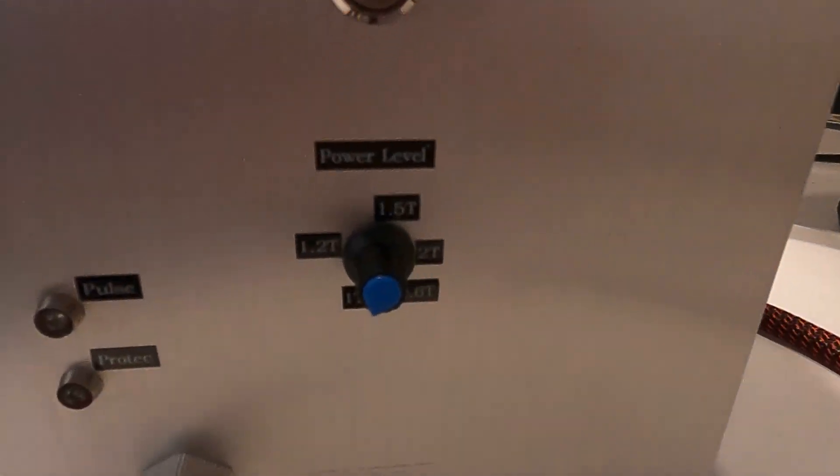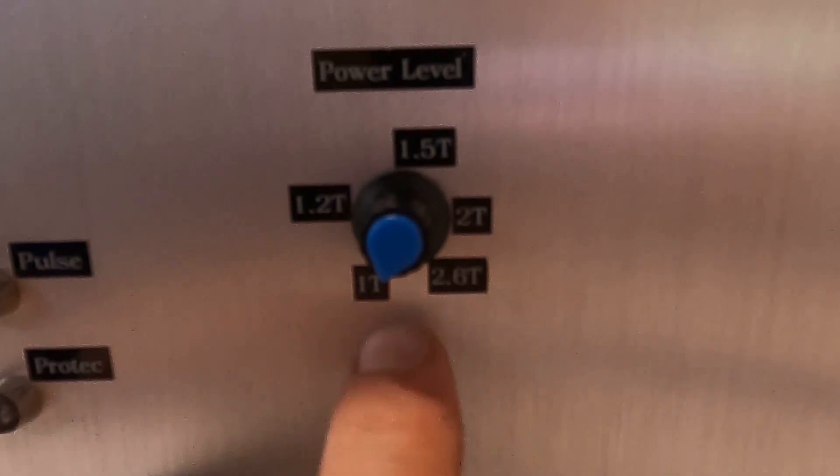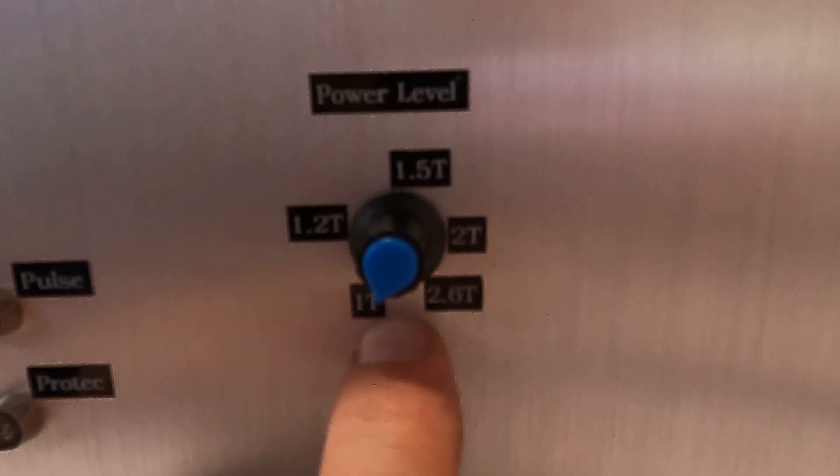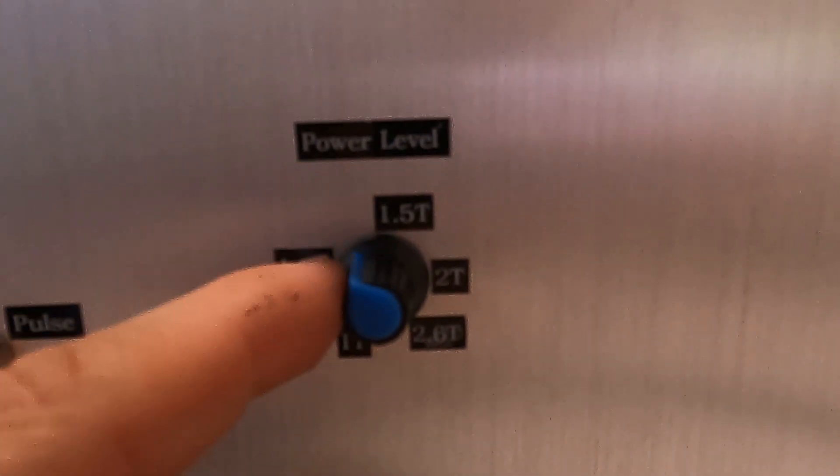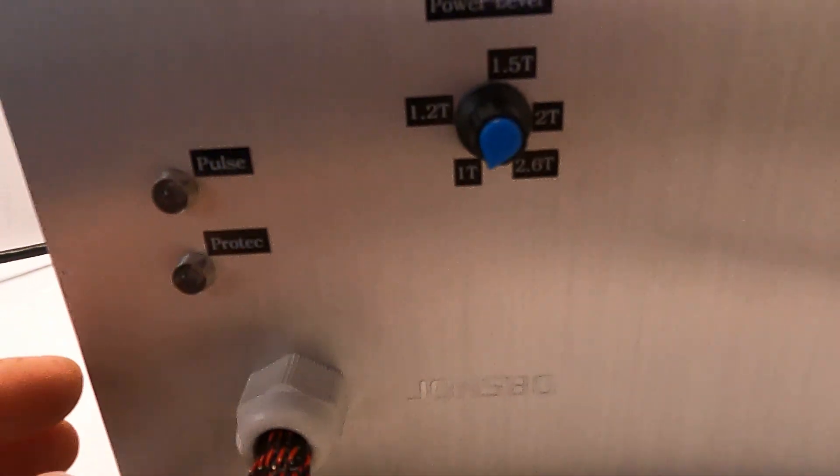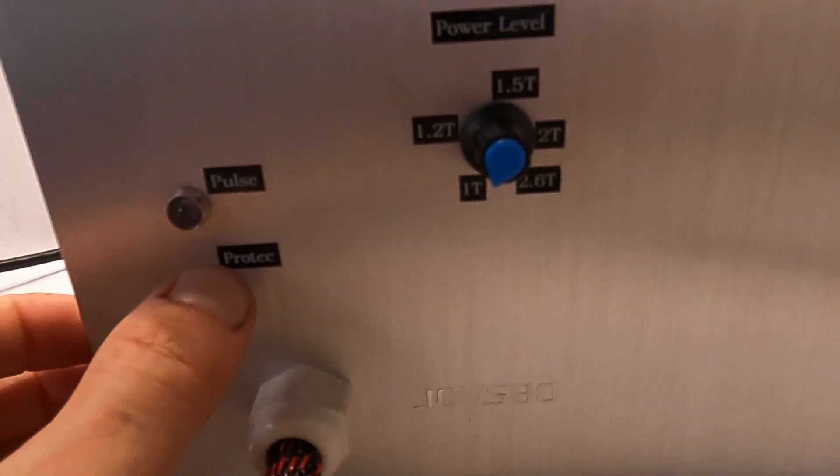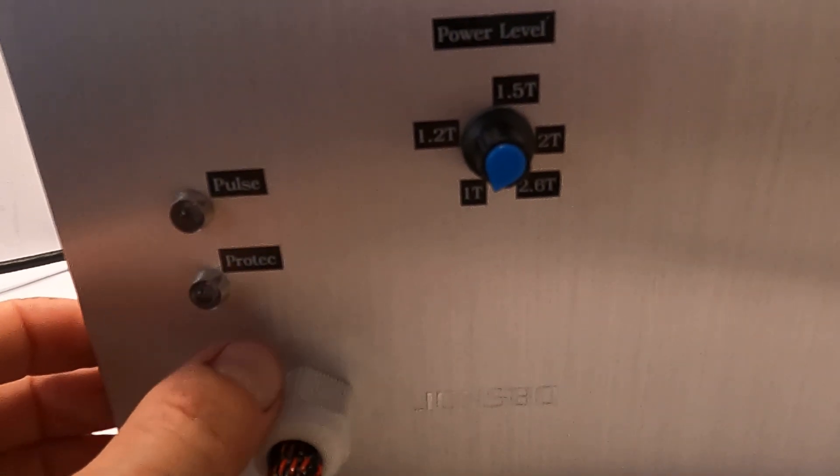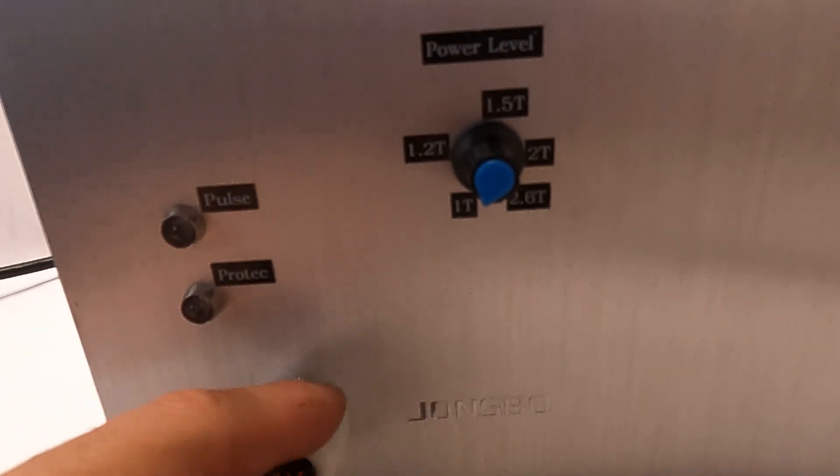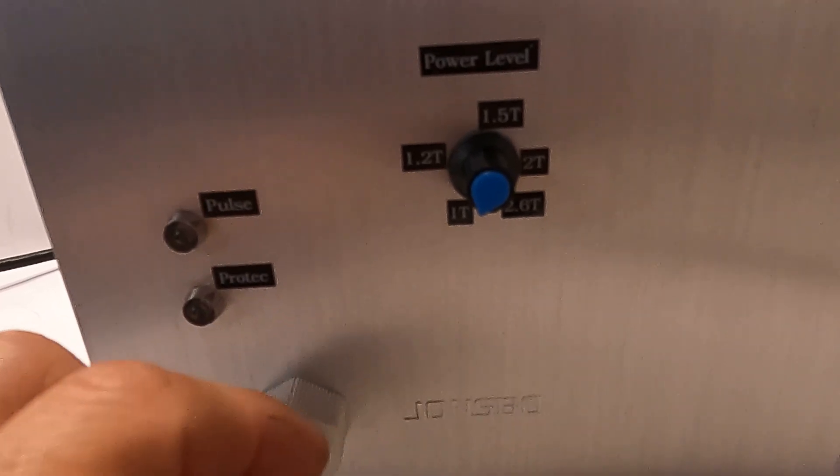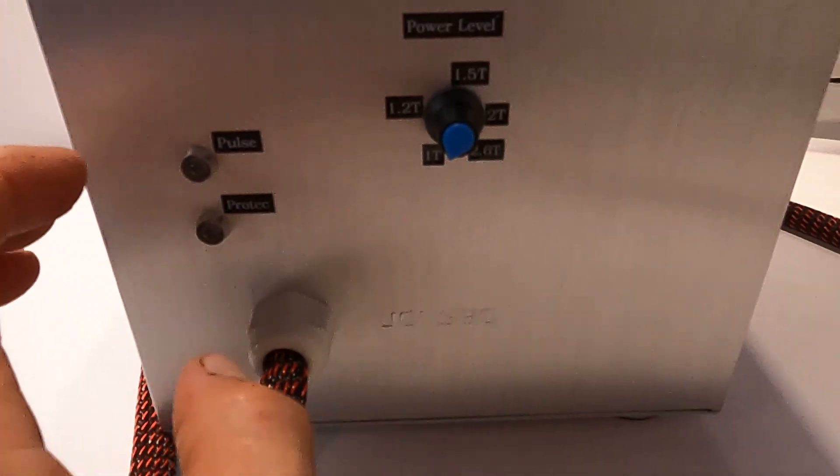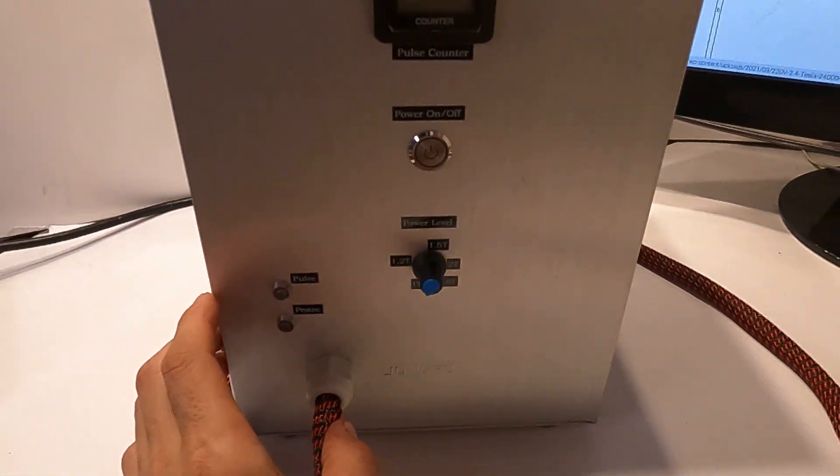Here you have a power dial. You can adjust between one Tesla and go all the way to 2.6 Tesla. Your pulse protection LED. There's multiple protections built inside when it comes to temperature.